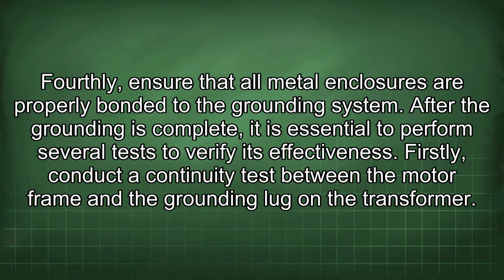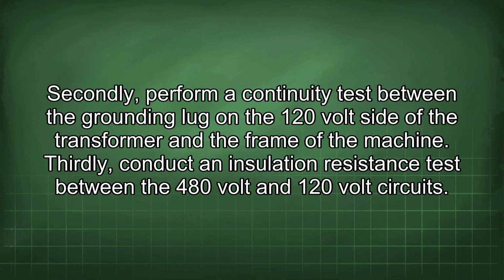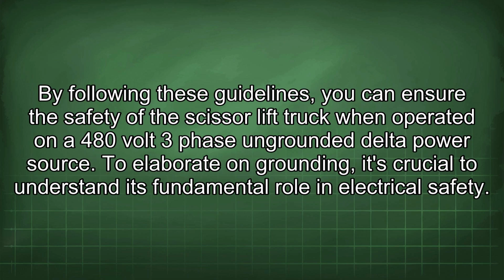After the grounding is complete, it is essential to perform several tests to verify its effectiveness. Firstly, conduct a continuity test between the motor frame and the grounding lug on the transformer. Secondly, perform a continuity test between the grounding lug on the 120-volt side of the transformer and the frame of the machine. Thirdly, conduct an insulation resistance test between the 480-volt and 120-volt circuits.